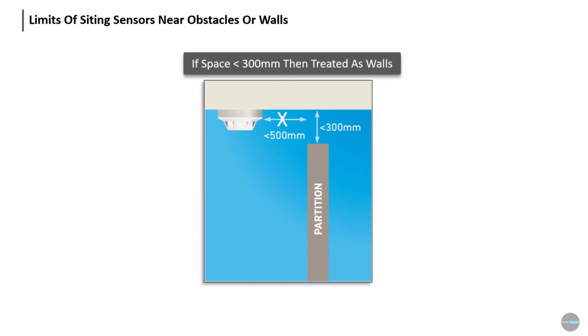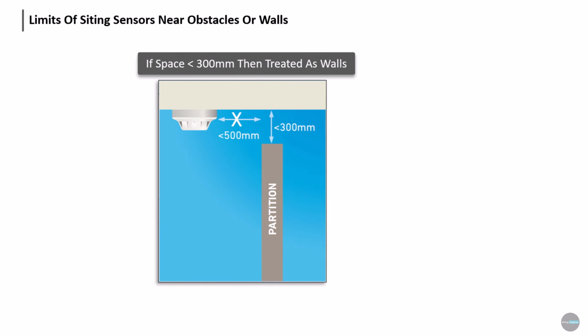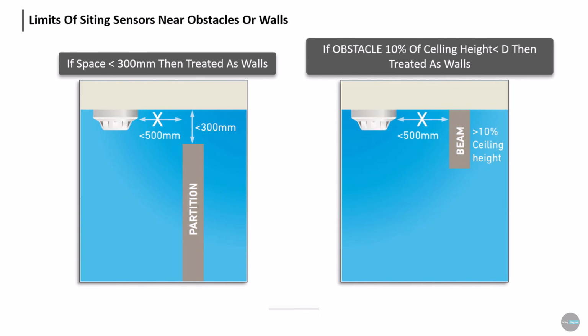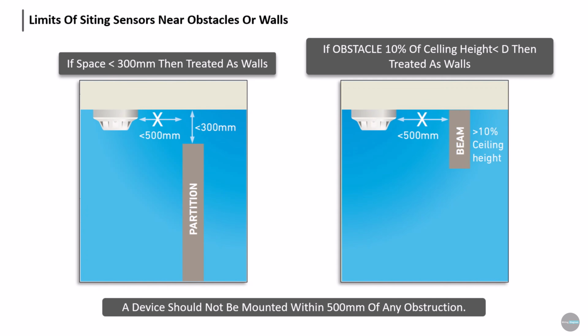3. If a room has a partition or rack, and the gap between the top of the partition or rack and the ceiling is less than 300 millimeters, or 4. if a room has a beam, and the beam depth is more than 10% of the floor-to-ceiling height, then we treat the partition, rack, or beam as a wall. This means the detector should not be installed within 500 millimeters of any such obstruction.